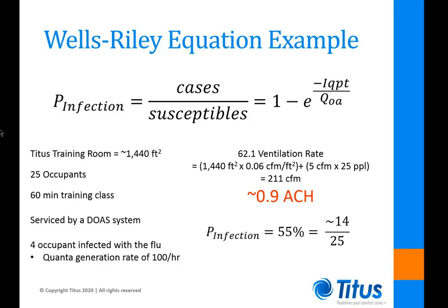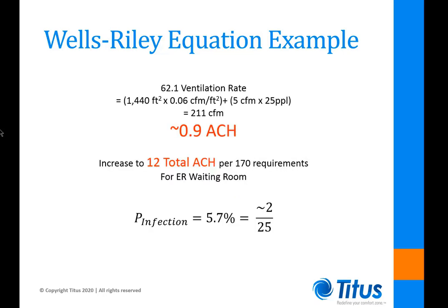In comparison, we can increase the air change rate to 12 air changes per hour — like what you'd see in an ER waiting room — with 100% exhaust. If we increase to 12 total air changes, the infection rate drops very significantly to less than 6%.